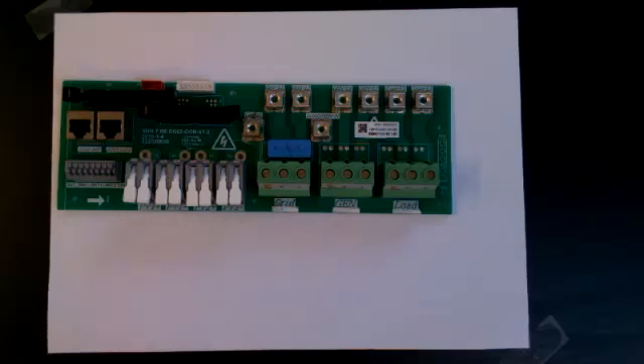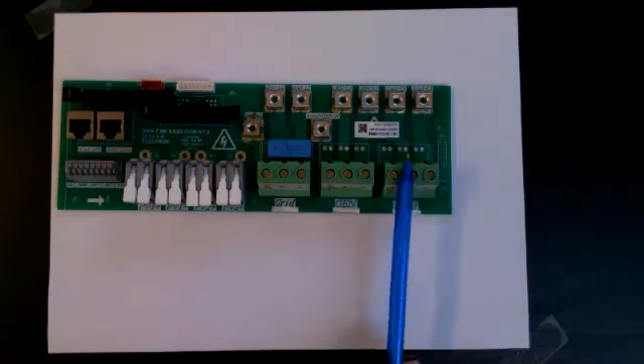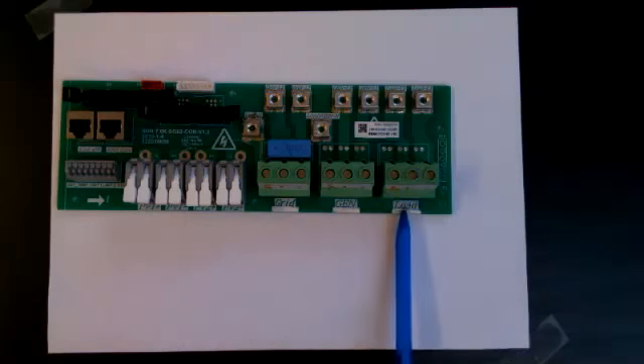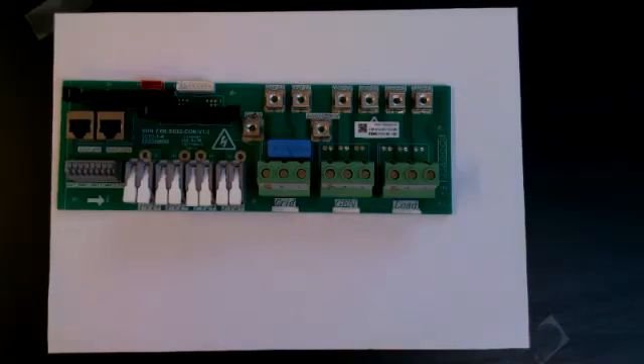It will still run from the solar. When the sun is shining and you've got grid there, it will run like a normal on-grid system. No problem. If you lose your power and you have load shedding, then your load side will continue to operate. So your lighting circuit, maybe security lighting, maybe some sockets, maybe some fans or whatever, but you don't want to connect too much, because that's going to soak up your batteries, and you just need to balance it. So always consider the two sides of it. I'll come back to that in a second.